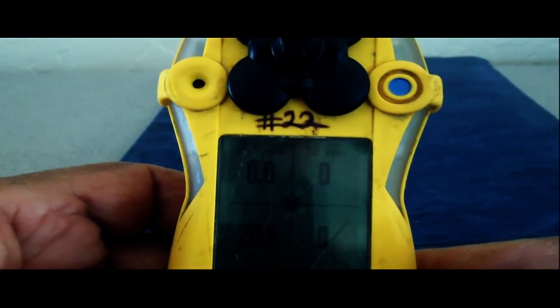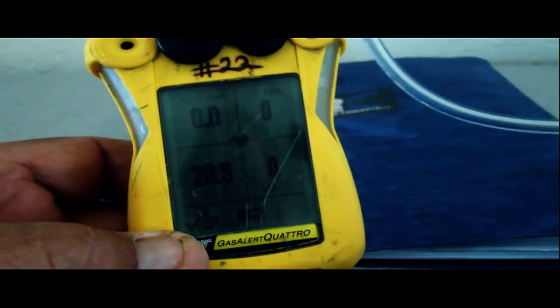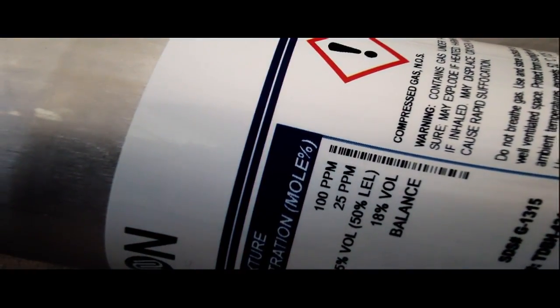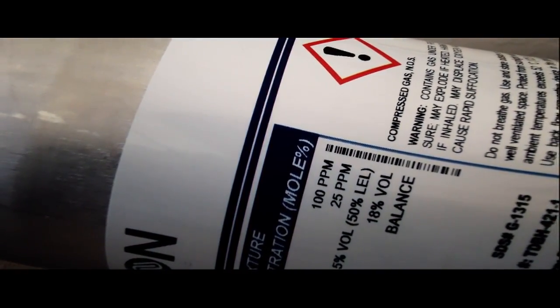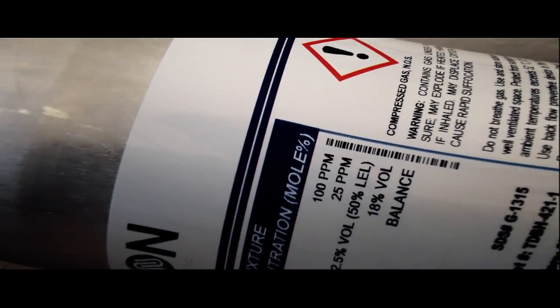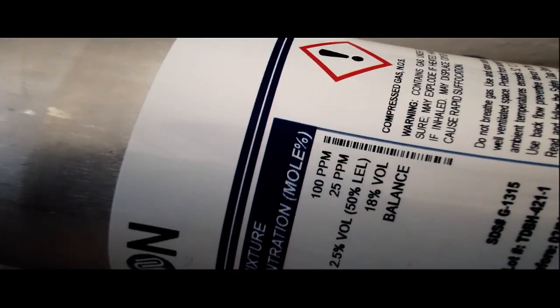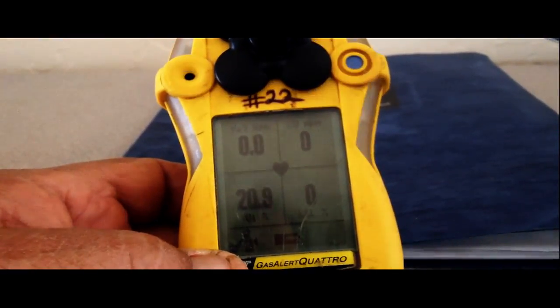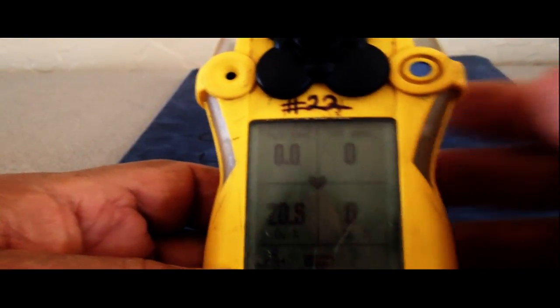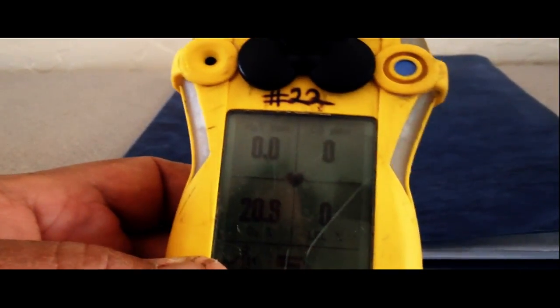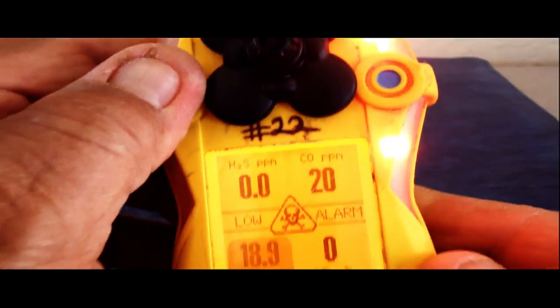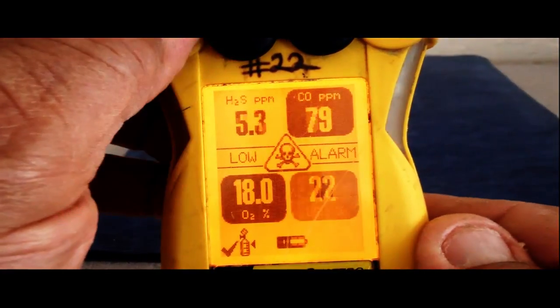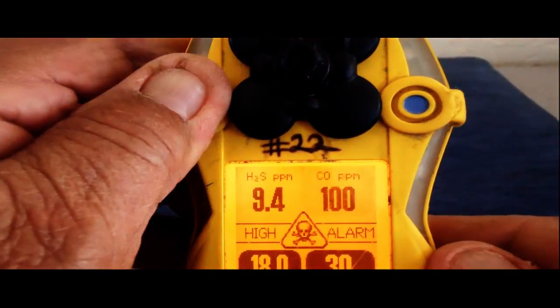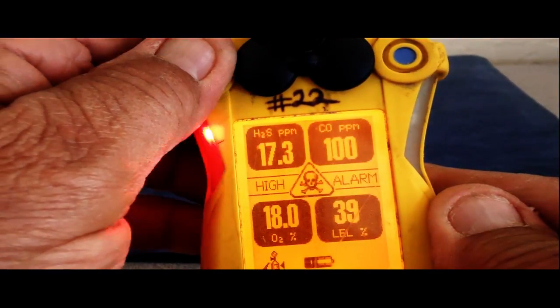So I've got my gas attached, or my calibration cap attached. We're going to look at the volume. We've done this before, but the volume is 100 parts per million carbon monoxide, 25 parts per million hydrogen sulfide, 50% LEL, and the volume on O2 is 18%. That will fluctuate when we do the bumping or the calibrating, and that's fine. We're looking for the toxins and the LEL to be dead nuts, however. So I'm going to turn my gas on, and it should start reading that shortly. So again, we're waiting for those sensors to read the appropriate values that are in that cylinder.